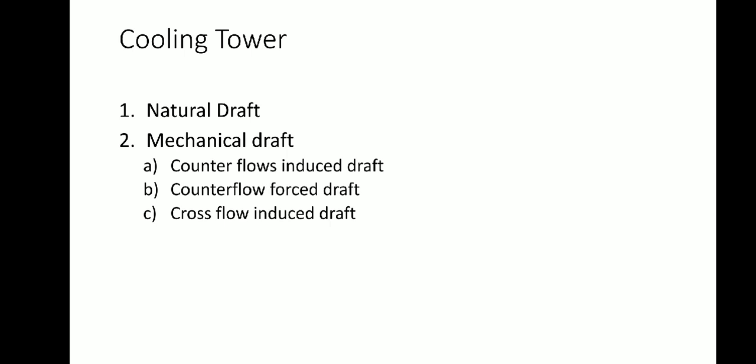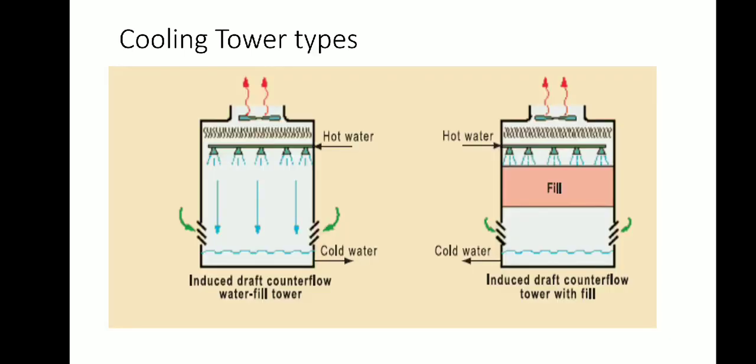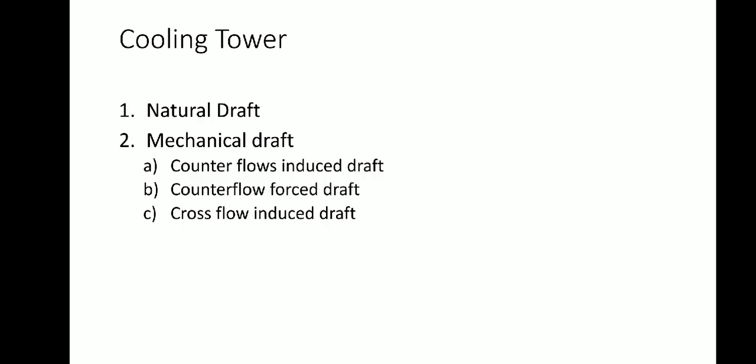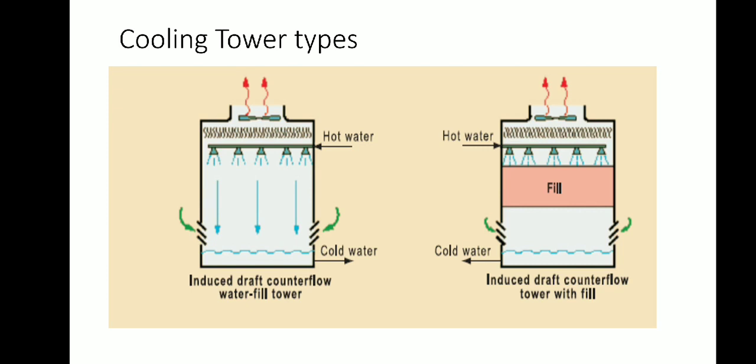Since mechanical draft cooling towers are much more widely used, the focus of this topic is also on them. In mechanical draft cooling towers, we have the following airflow arrangements: one is counterflow induced draft, second counterflow forced draft, and third crossflow induced draft. In a counterflow induced draft design, hot water enters the top while air is introduced at the bottom and exits at the top. Both forced and induced draft fans are used.